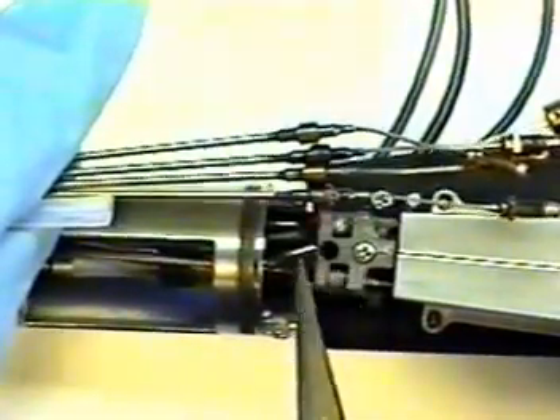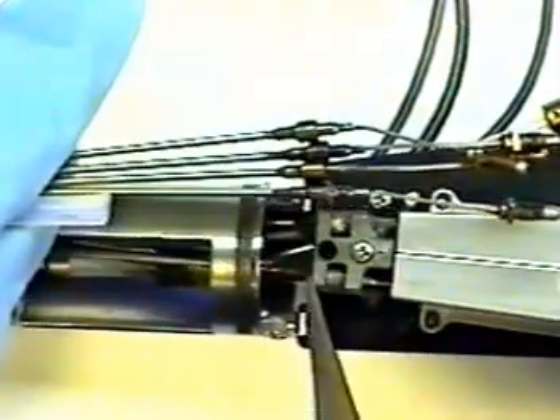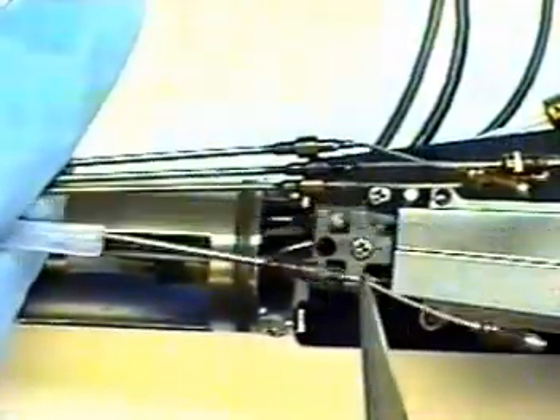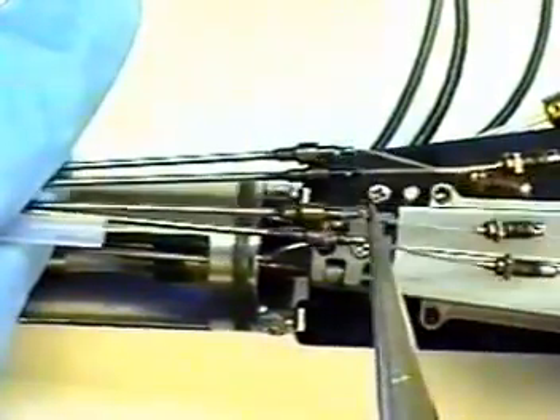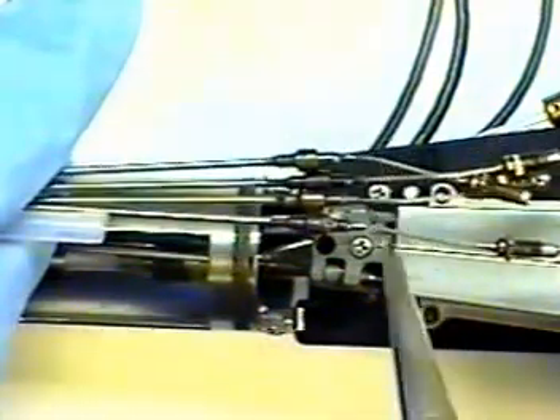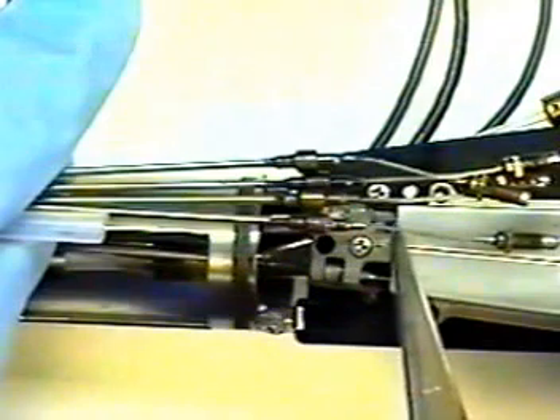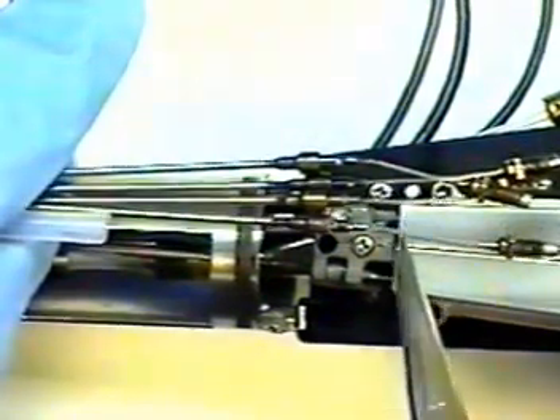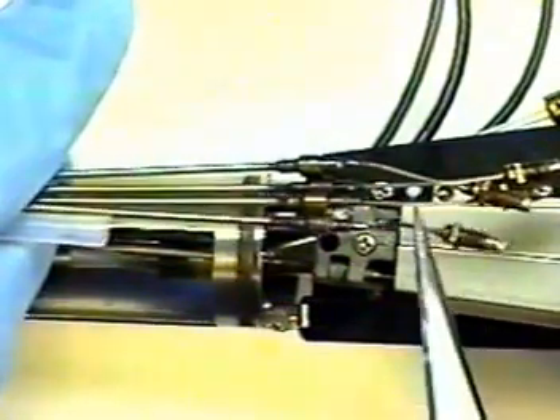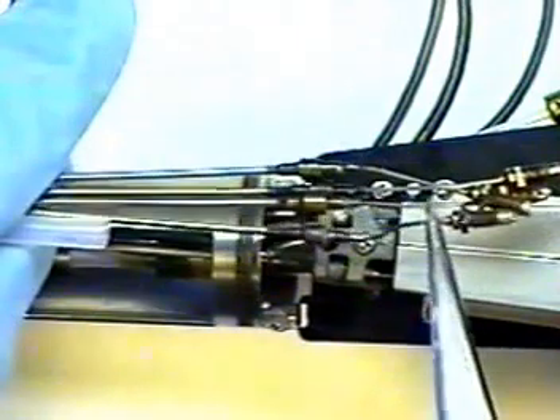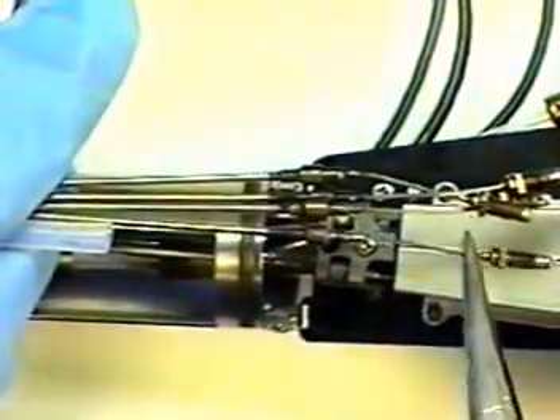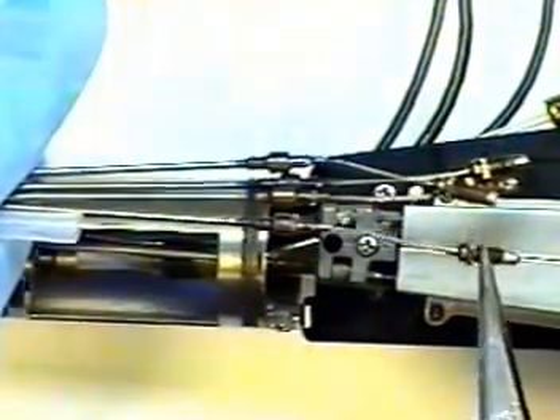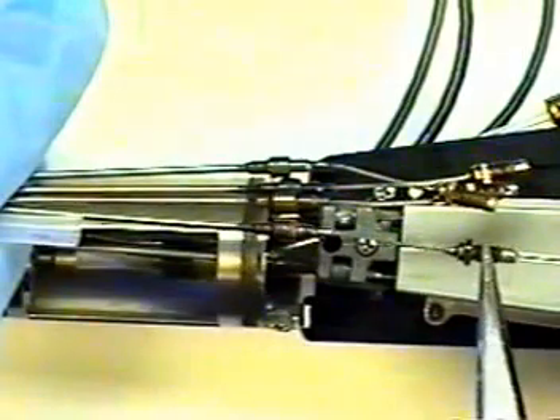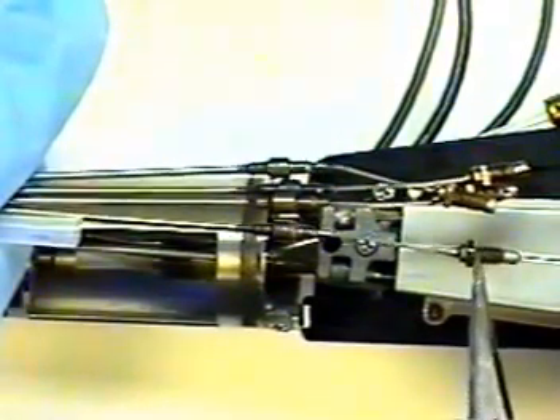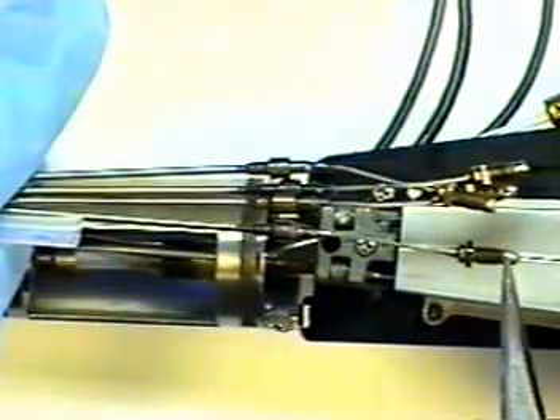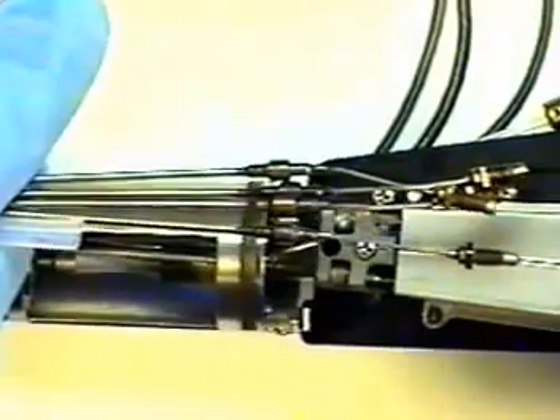Be sure when pulling these through and reattaching that you have put the proper color codes for each angulation wire. Again, red is up, black is down, green is left, and silver or no color is right. We can test this before final assembly to be sure that the angulation wires are properly installed. Reattach cables to each up, down, left, right ferrules, and tightening ferrule down approximately 2 to 3 millimeters from the control stopper. We will test for plain angulation again with final assembly.